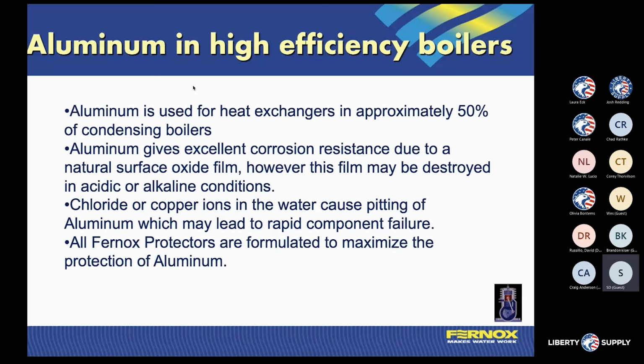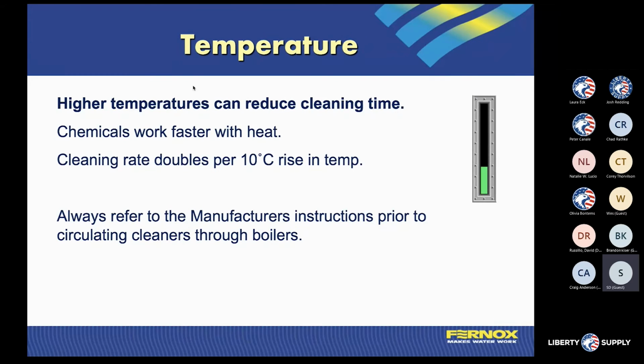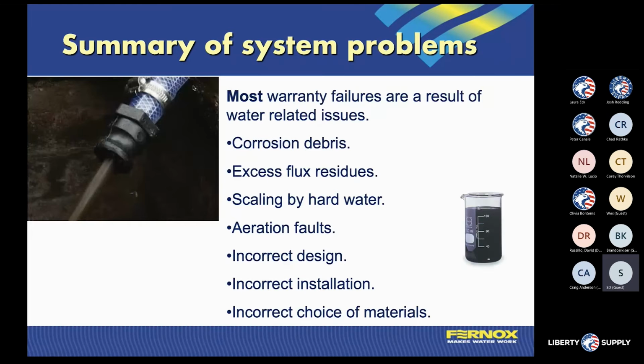These are all applications that we're seeing as a byproduct or a secondary factor to water quality. Because we're going to look at cleaning the systems, the higher the temperature we can run that system out, the more it's going to help us get as much of the debris out as fast as possible. At the end of the day, we're going to end up with a system that's full of water that has particulates that are going to inhibit flow and inhibit heat transfer, and are going to affect your AFUE of your system.